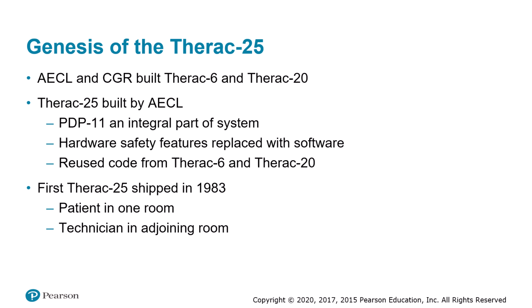The Therac-25 was a large machine that was placed in its own room, and shielding in the walls, ceiling, and the floor of the room prevented outsiders from being exposed to radiation. A television camera, microphone, and speaker in the room allowed the technician in an adjoining room to view and communicate with the patient undergoing treatment. In a 20-month period between June of 1985 and January of 1987, the Therac-25 administered massive overdoses to 6 patients, causing the deaths of 3 of them.